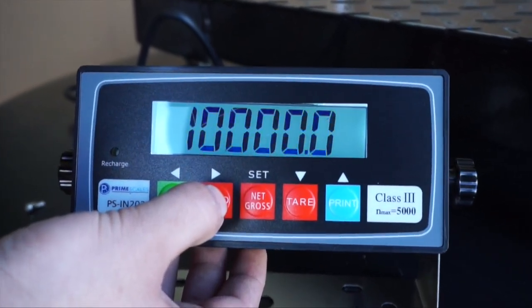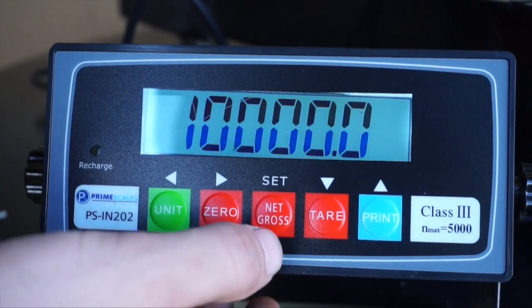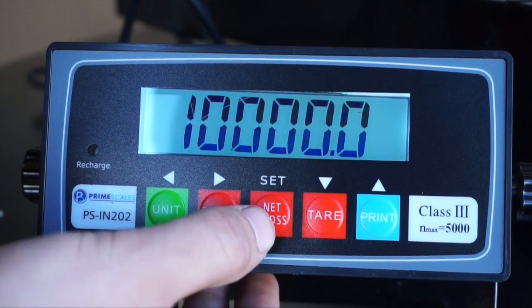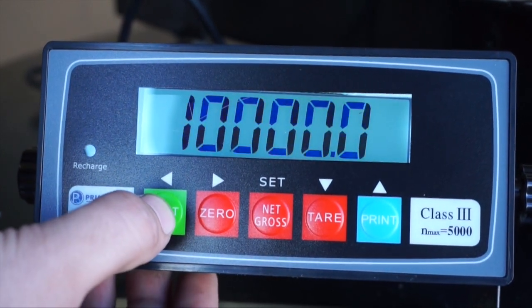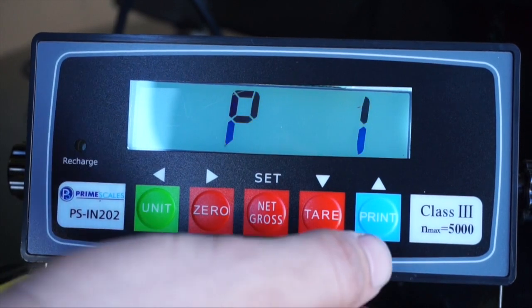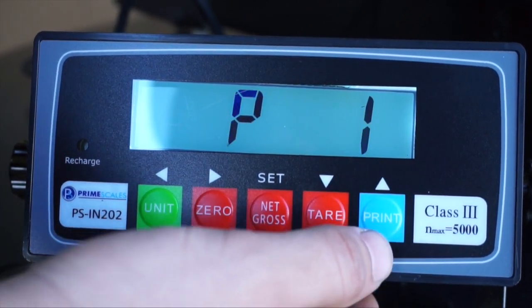In this video, we will use 10,000 pound capacity times one pound accuracy. After setting to 10,000 pounds capacity, press net gross button to save setting. Press unit to go back to P1.